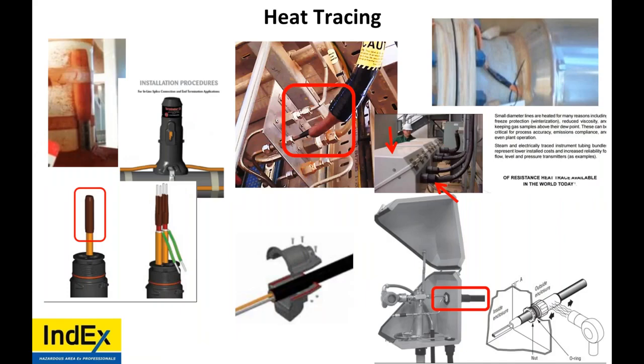Heat tracing. I'm not going to go too deep into this one, but a certain manufacturer calls for the terminations to be in an Ex e kit, but somehow it ends up not being that way in the field, whether it be tube trace bundle or regular heat trace. In Australia, they didn't use these instrument huts. It would have been a very good idea. Perfect way to terminate these terminations. All terminations shall be an ATEX type enclosure. This little boot is not an EX enclosure.